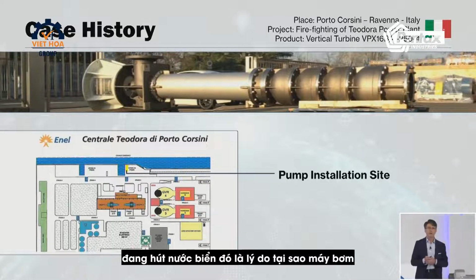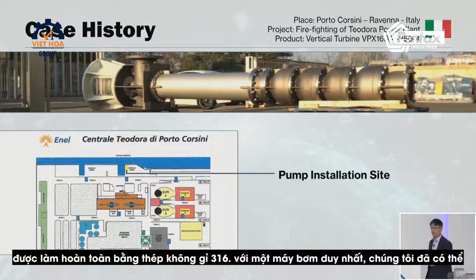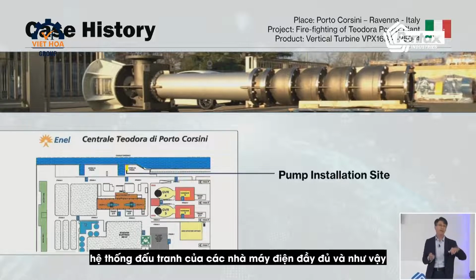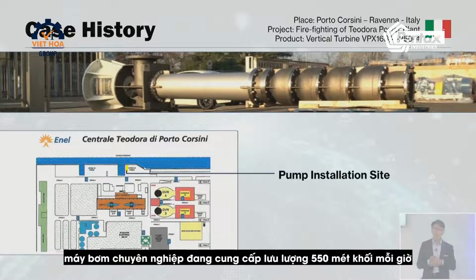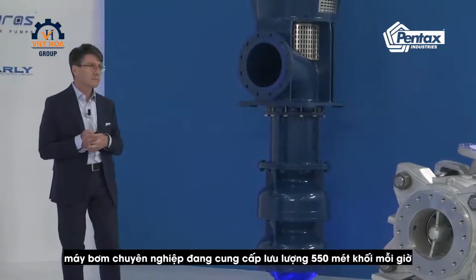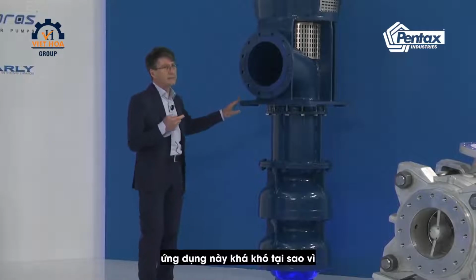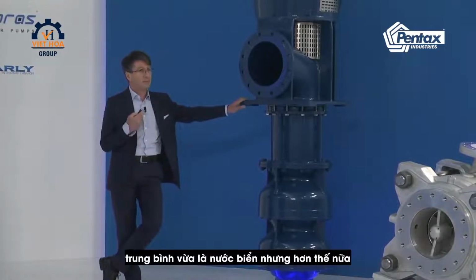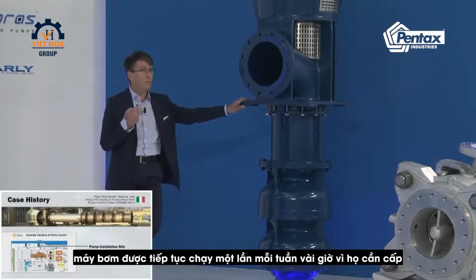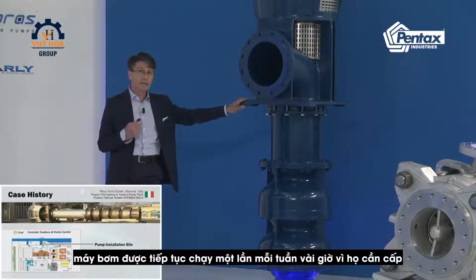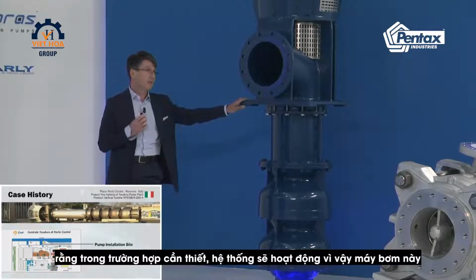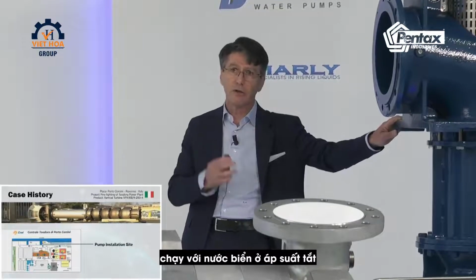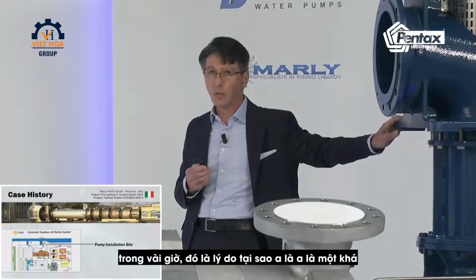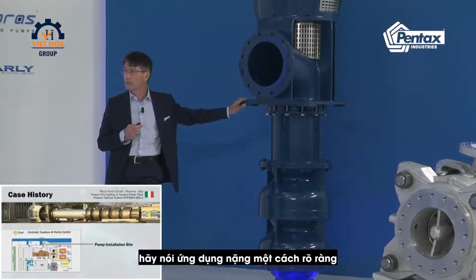That's why the pump was made completely of stainless steel 316. With one unique pump, we were able to provide the extinguish system, so the firefighting system of the full power plants. So the pump is providing 550 cubic meter per hour flow. The application is quite hard. Why? Because of the medium. Medium is the seawater, but moreover, the pump is kept running once per week, few hours, because they need to grant that in case of needs, the system is operative. So this pump is running with the seawater at a shut-off pressure for a few hours. That's why it is a quite, let's say, heavy-duty application, I would say.